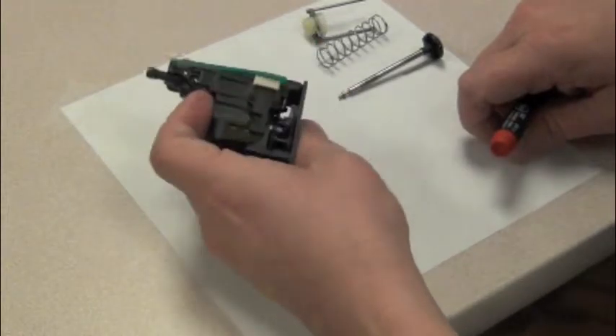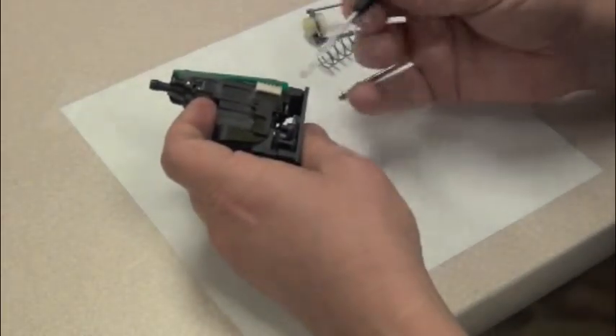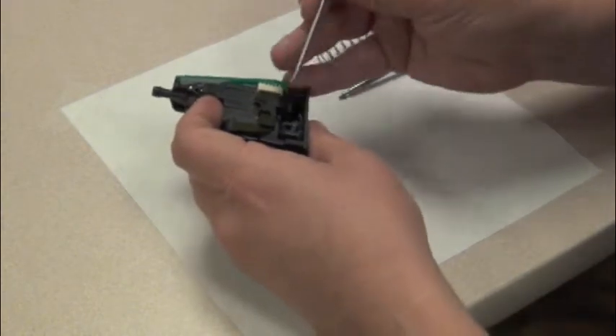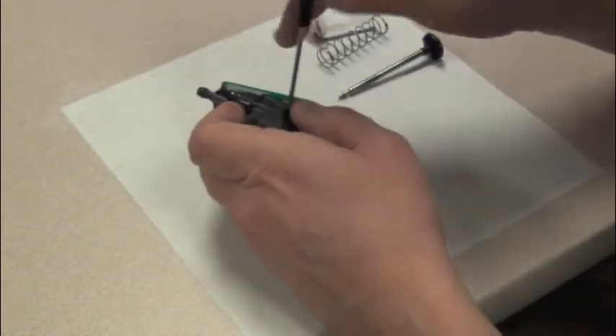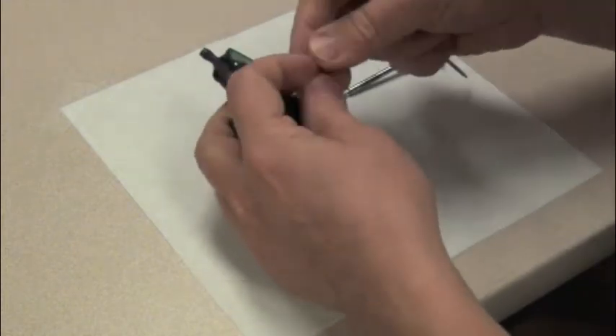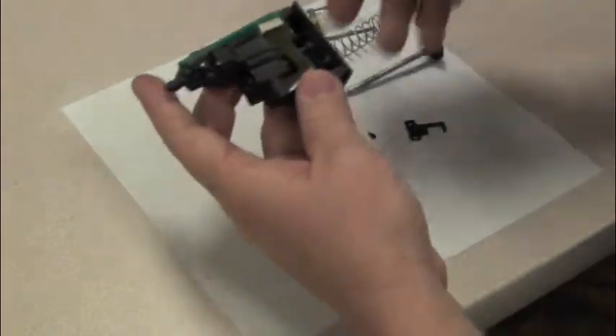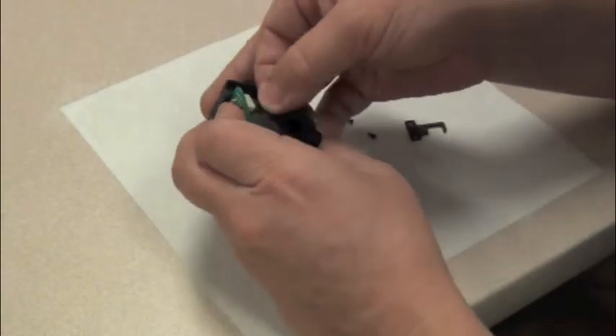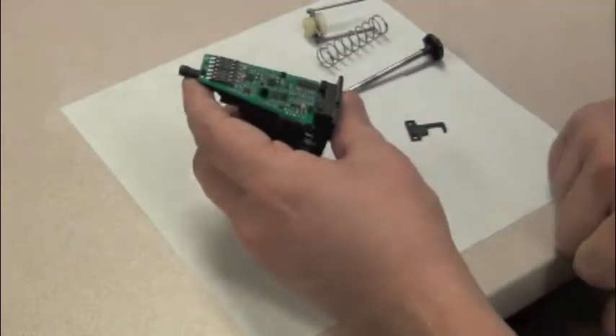I'm going to turn the spindle assembly over and remove the two screws on the theta cable bracket, remove the bracket, take the theta motor cable and slide it out of the connector, then turn the spindle over.